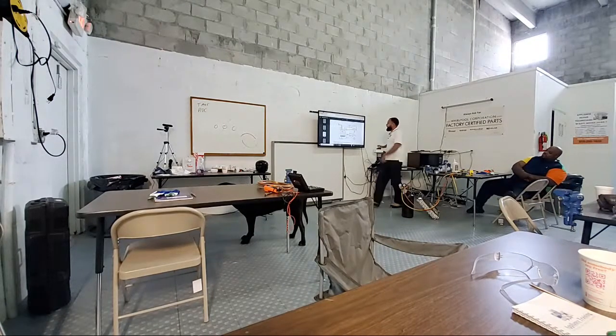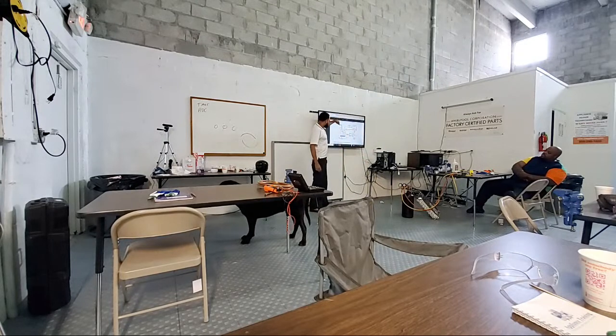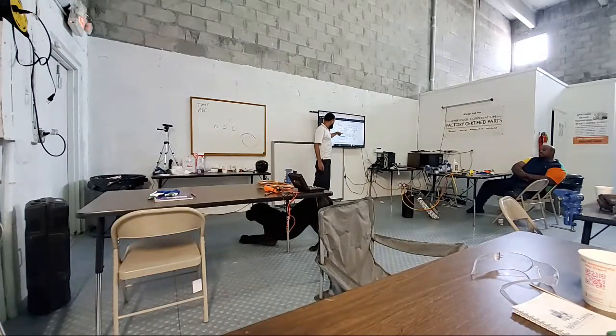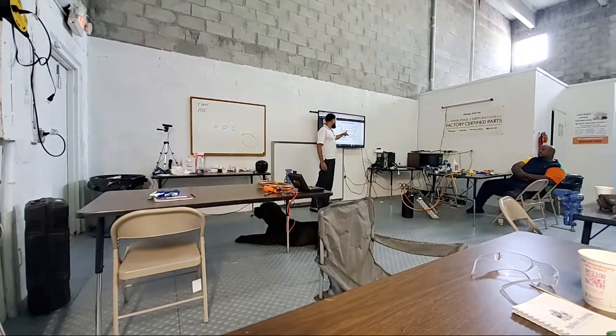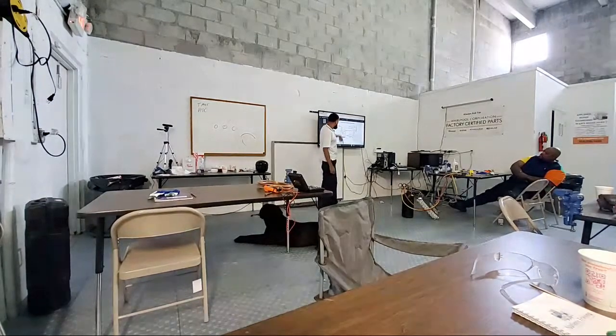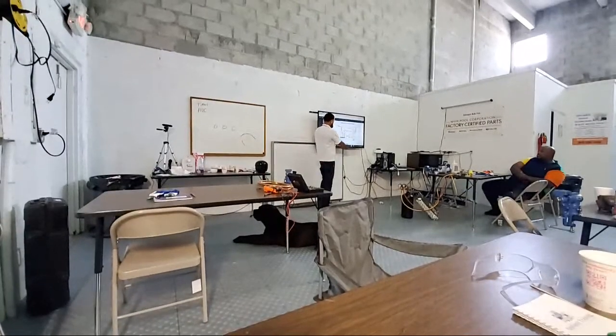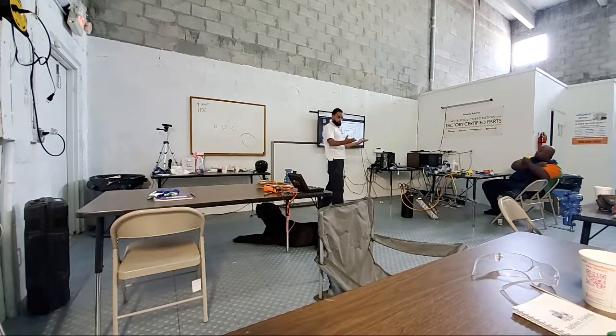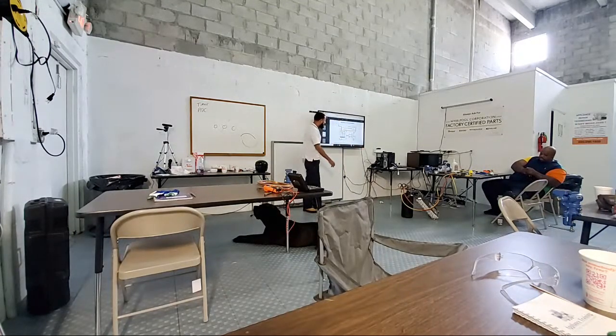All right, this is a better picture. Here's L1, coming into our defrost control, right? It comes out pin 6, goes over that wire. Okay, so that's just letting us know we got 120. We want to make sure that our board is getting 120. How do you do that? L1 goes into black, and here's your neutral wire. Remember, you need 2 points of reference to verify 120. We just want to make sure we're getting 120 to the board.